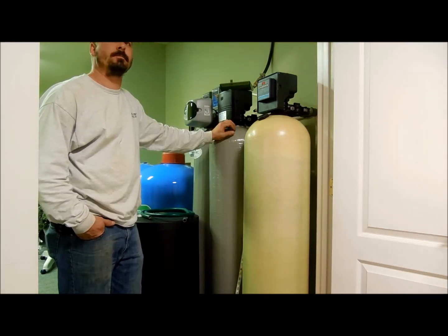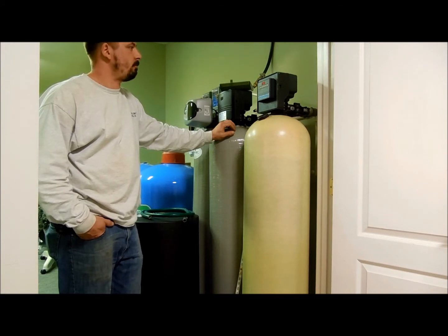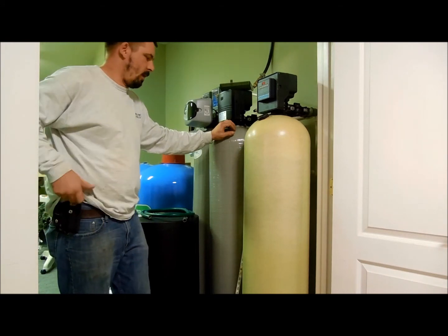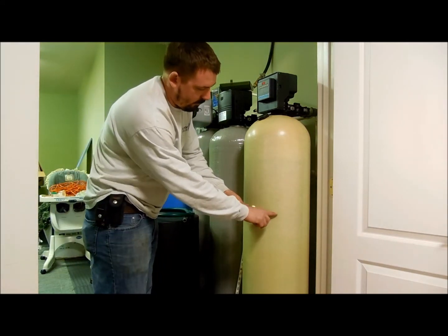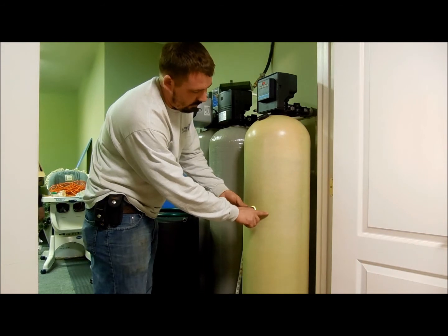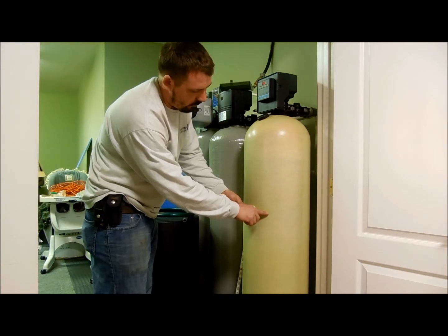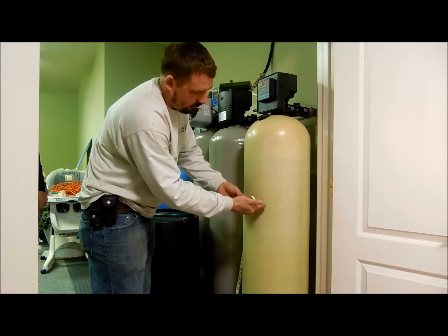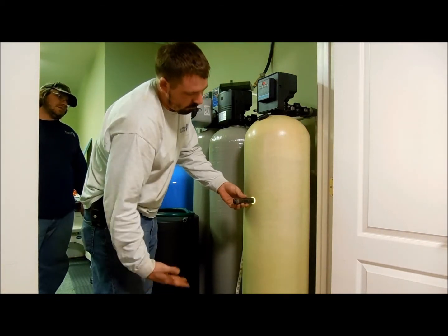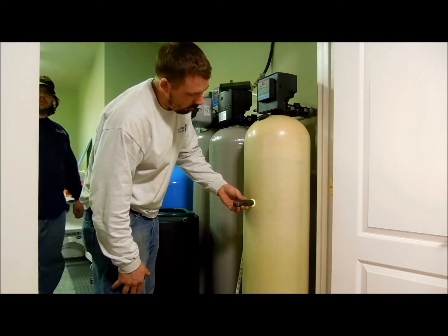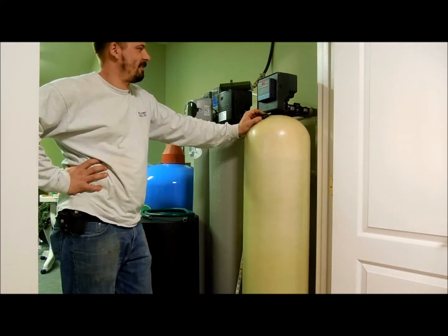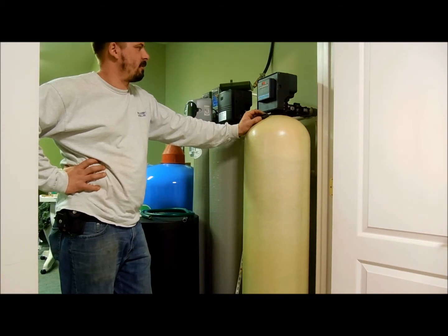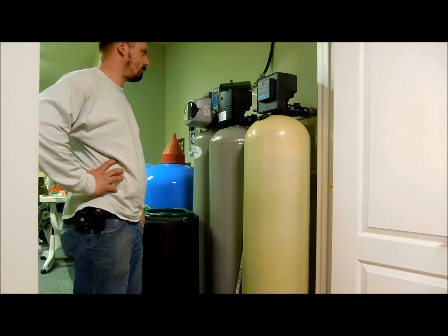And Steve, can you visually see anything for the backwash with a bright flashlight in that particular unit? You might be able to see, if we have the lights off, you can see it, but the mineral level is right here. And typically when it's in backwash, you'll notice that the mineral bed itself will start to lift, showing that it's really flowing the water and cleaning itself. We usually backwash the filter just for a few minutes to begin with to remove any sediment that is on the top of the filter media.